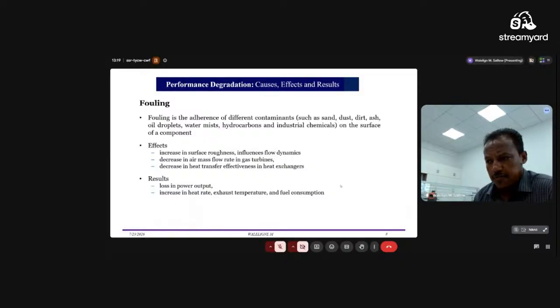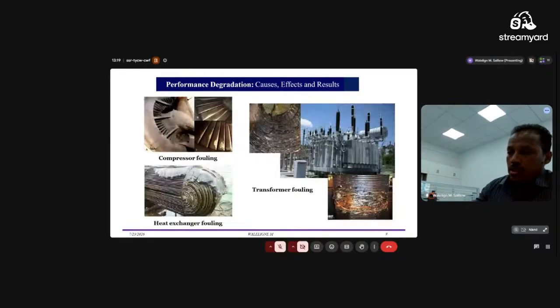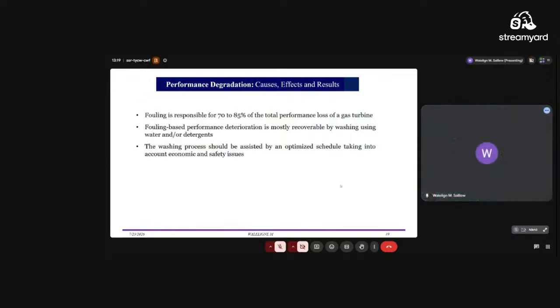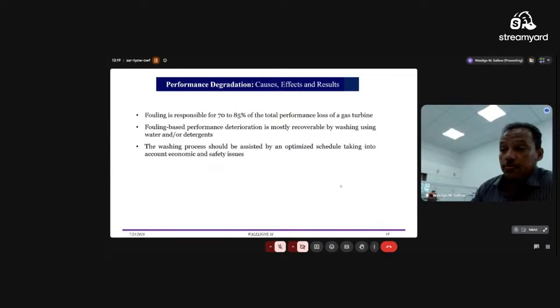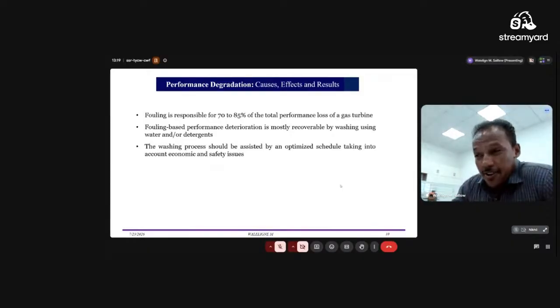So it increases surface roughness, influences flow dynamics, decreases the air mass flow rate in the gas turbine, and decreases heat transfer effectiveness in the heat exchanger. As you can see from the picture here, there are compressor fouling, transformer fouling, and heat exchanger fouling. Generally, fouling is responsible for 70 to 85% of the performance deterioration of the gas turbine. So the most common fault in a gas turbine is fouling. But the good part is that the performance decline can be recovered through scheduled washing of the component.